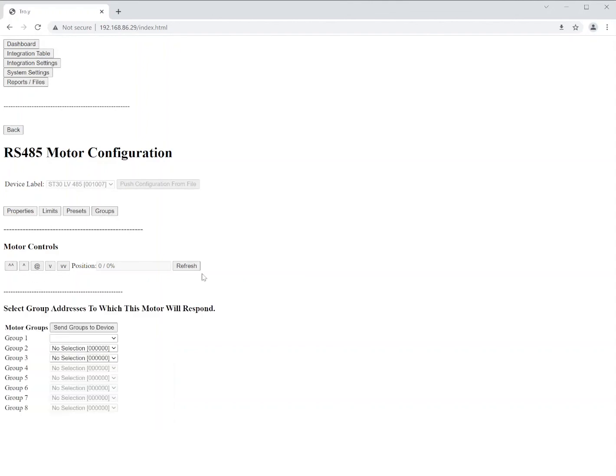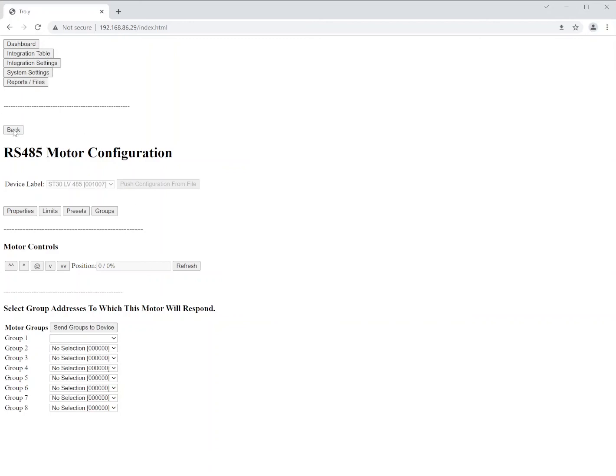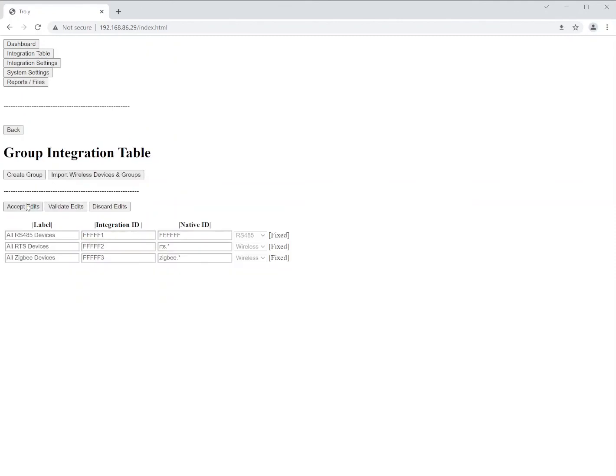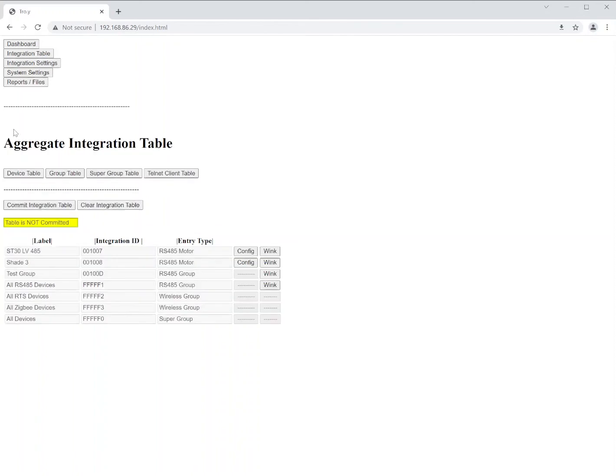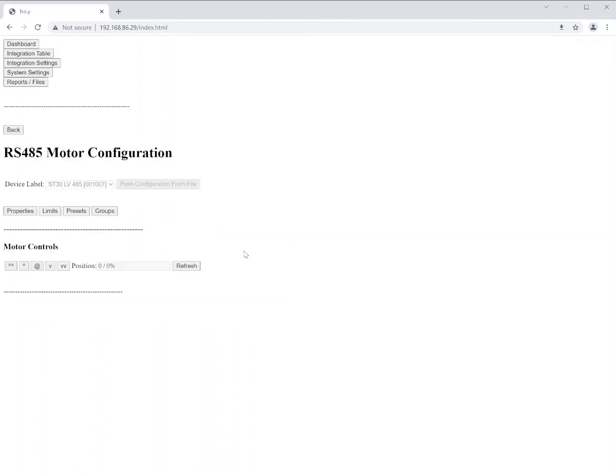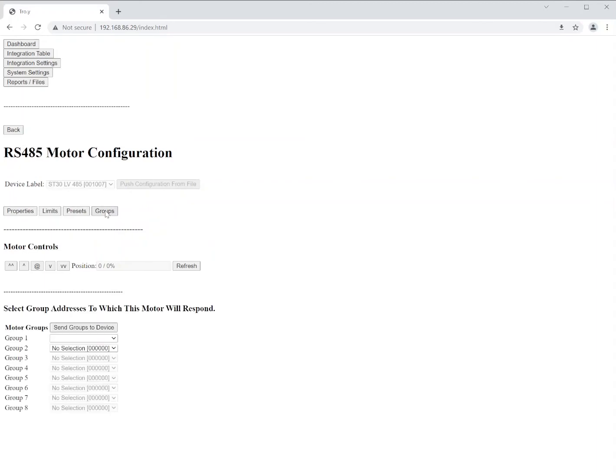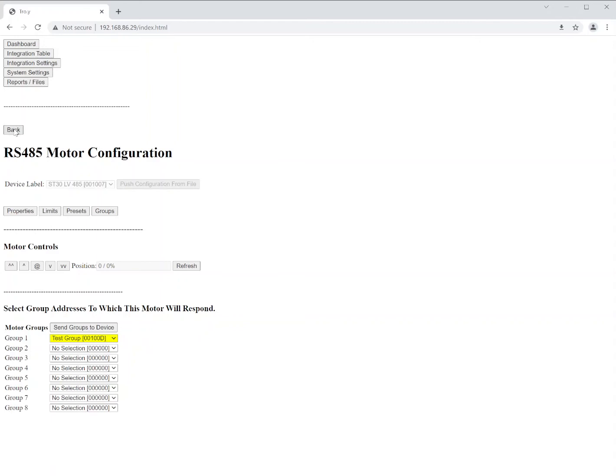Now onto groups. In groups, in here, what we do is you would go into a group section and create and define any groups that you may need for the system. And then you would simply apply those to the groups here. So in this case, let's go back. We're going to go back and then we'll go to the groups table and create a new table. So we're going to create a group. Okay. Once we've created our group, we need to accept the edits that we have. Then we can go to the back button and we can again go back into the configuration of our motor into our group section. And you'll see now that this dropdown will contain the test group that I just created. So we can select that group and that motor will now respond anytime that that group is called. So this motor is now part of the test group. And again, we'll go back.